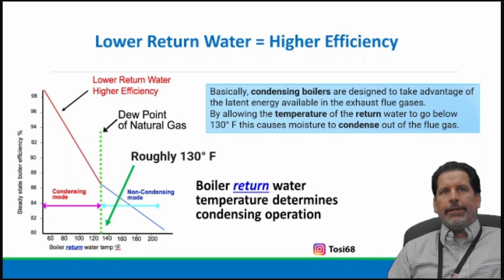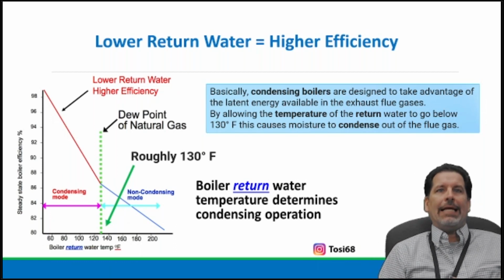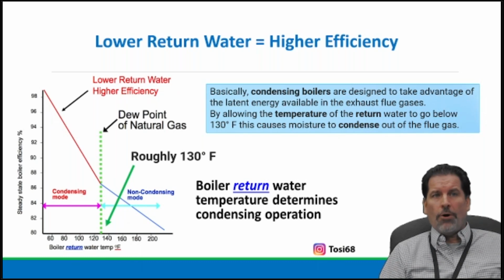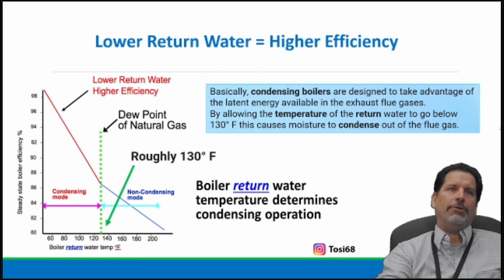A lot going on here, right? A condensing boiler is designed to take advantage of the latent energy available in the exhaust flue gases, allowing the temperature of the return water to go below 130. The moisture is able to condense, again, vapor to a liquid. That's the starting point. 130 is the starting point. But look at our efficiency line here.